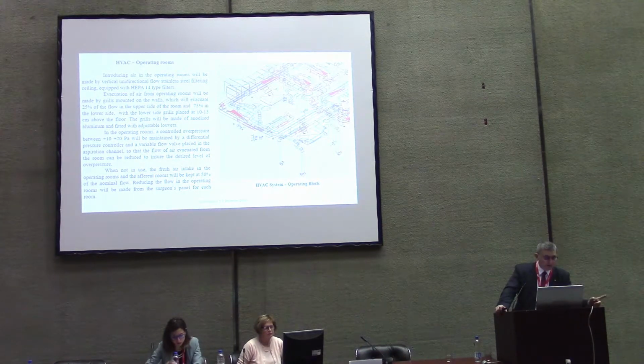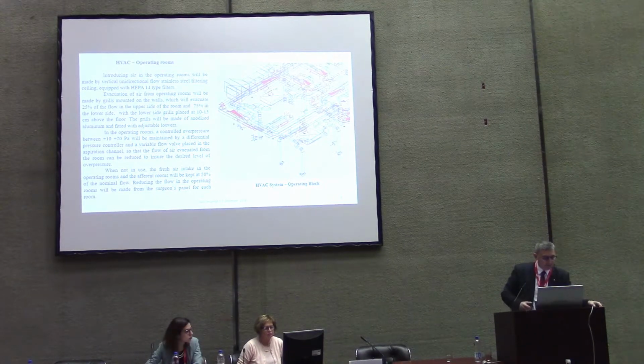It's very important to keep this overpressure in the operating room. We will see in comparison with the laboratory, where we have under pressure. When it's not in use, the operating room will be kept at 50% of the nominal flow.